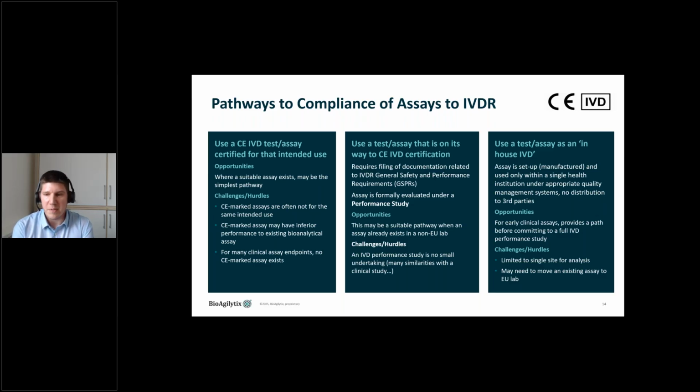The requirements being that the lab that is manufacturing that test is a single health institution in the EU and has an appropriate quality management system in place and complies with ISO 15189, and there's no distribution to third parties. So the test is purely manufactured and used in the same facility. Especially for early clinical trials, this provides, in some cases, a quicker access to start testing already in phase 1, before you need to put a lot of effort into running a performance study.